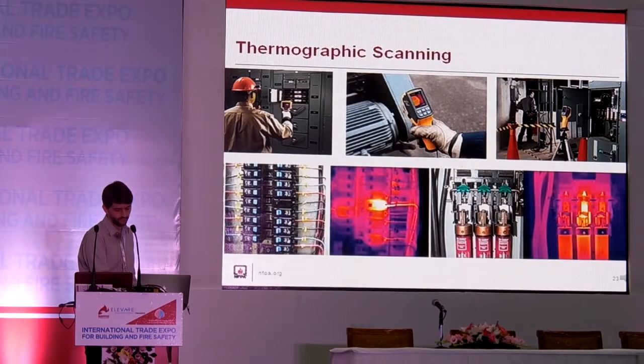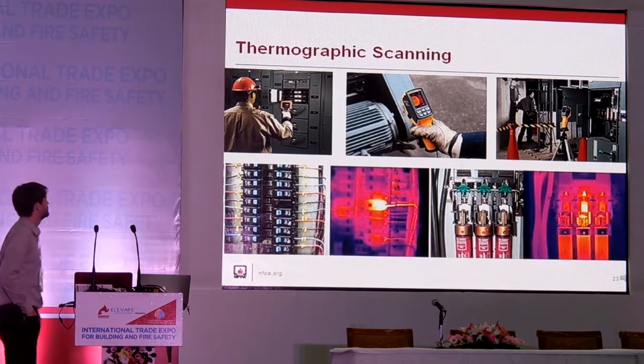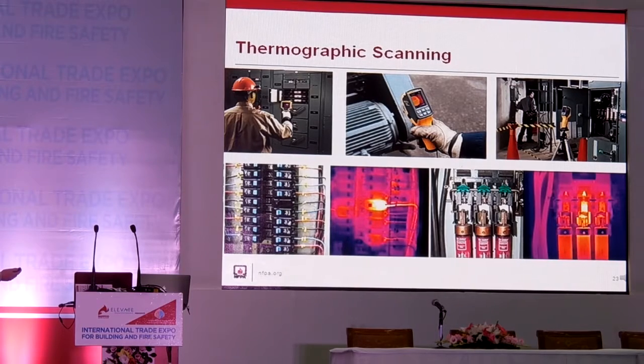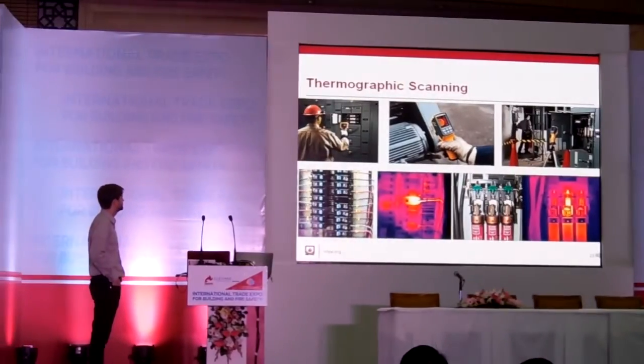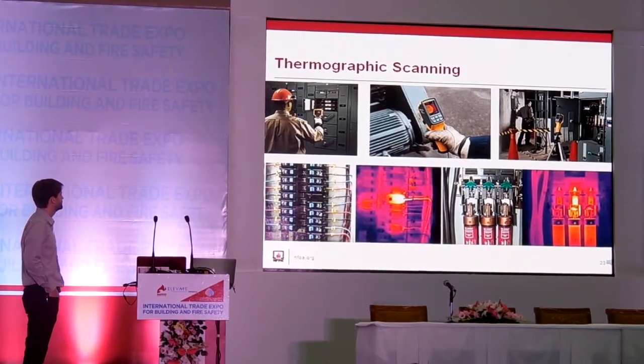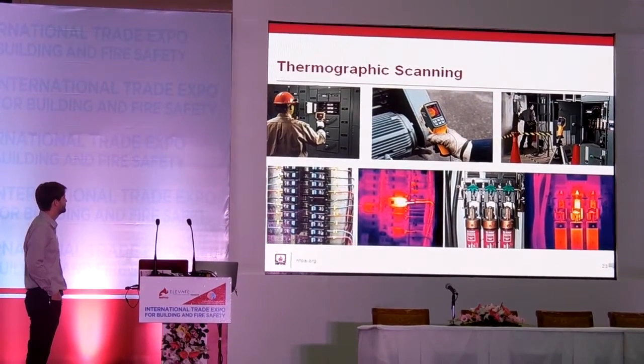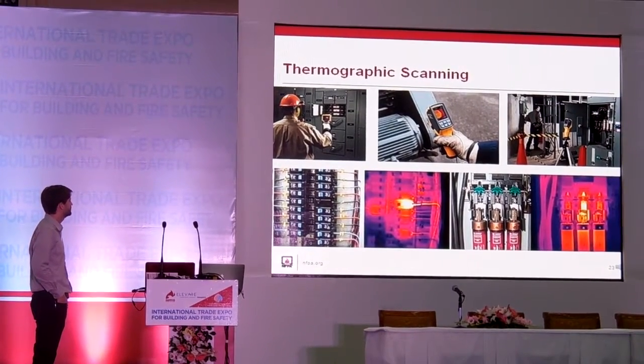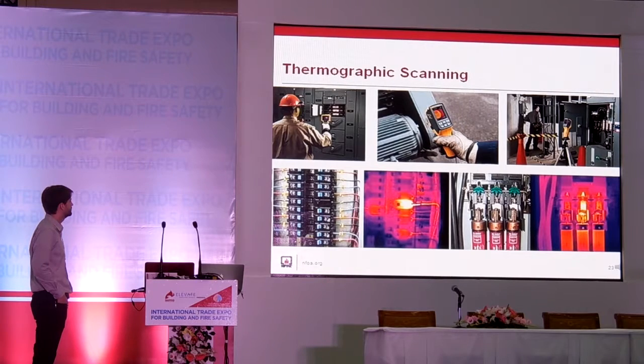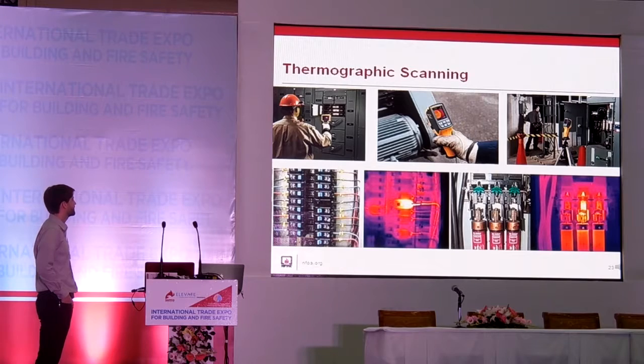Thermographic or infrared scanning is an important data collection tool. Determining whether there are hotspots at connections within bus bar arrangements and equipment, at motors, including at motor bearings. All of these data points can be collected and analyzed to determine whether there are impending equipment failure locations. Simple visual inspection of items like a panel board or a safety switch are typically not going to yield the necessary information as to whether there are problems that may occur within that equipment.